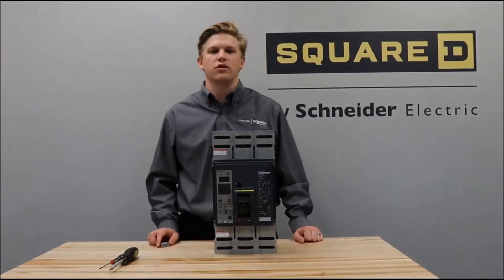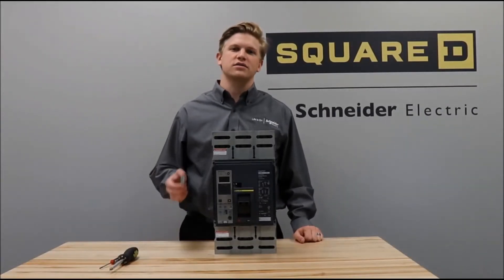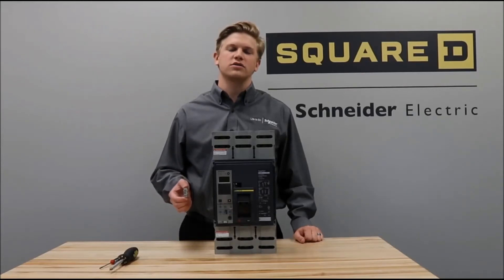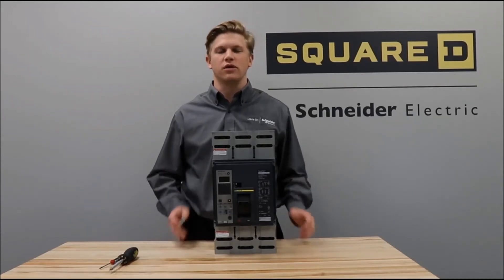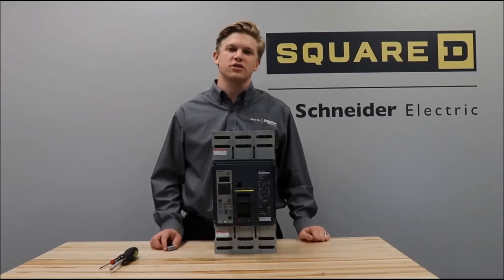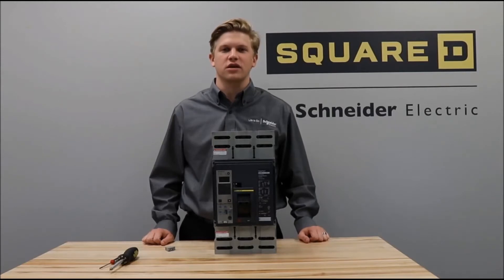In this video we'll be showing you how to install the S29450 AUX overcurrent trip or alarm switch into a PowerPact P-frame circuit breaker. Before installation, always make sure to read all the safety information in the instructions provided with the kit, and never work on energized equipment.